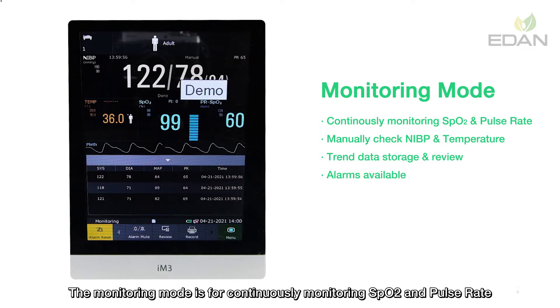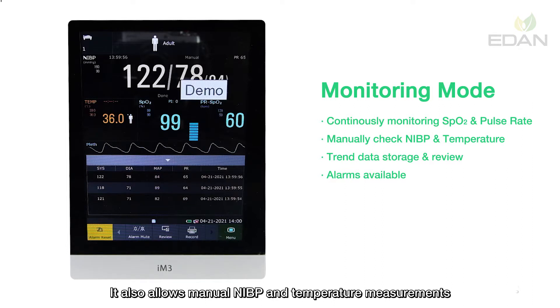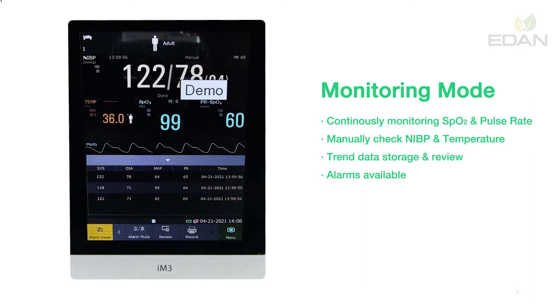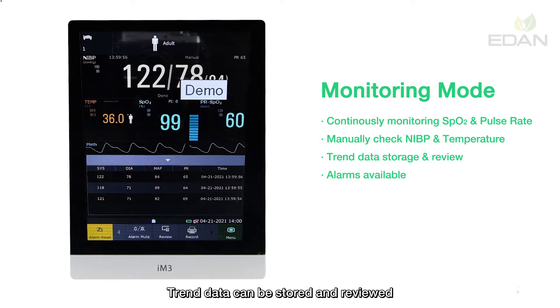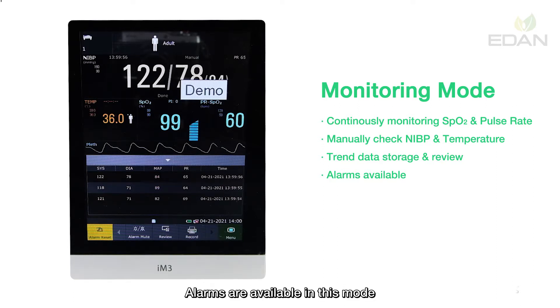The monitoring mode is for continuously monitoring SpO2 and pulse rate. It also allows manual NIBP and temperature measurements. Trend data can be stored and reviewed, and alarms are available in this mode.